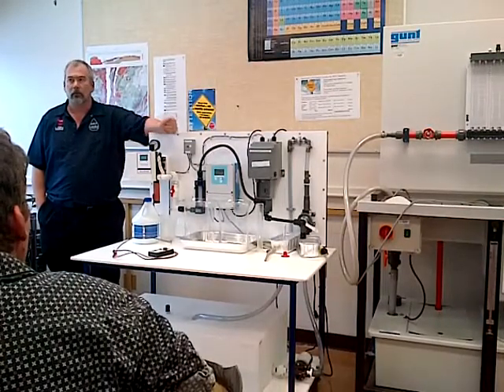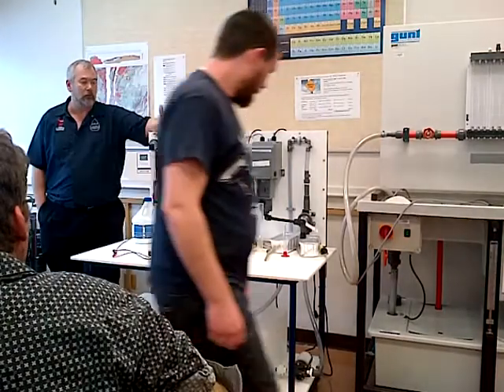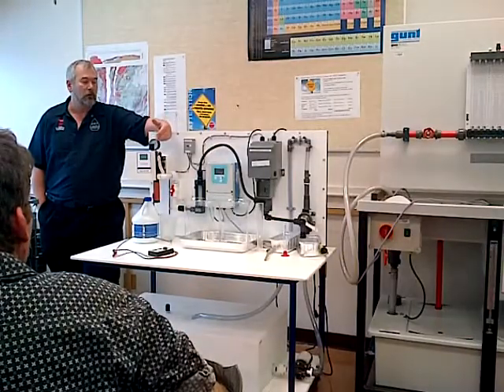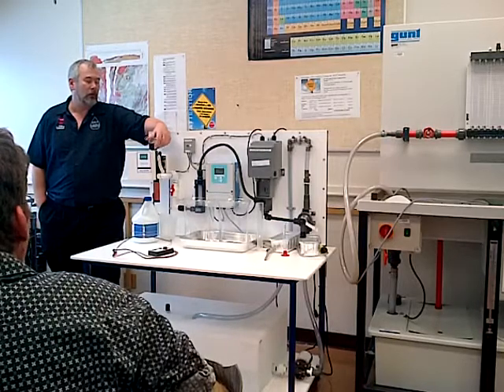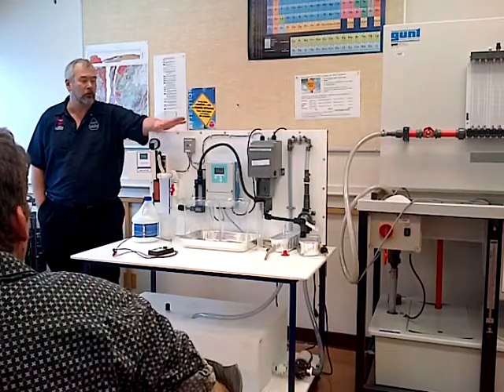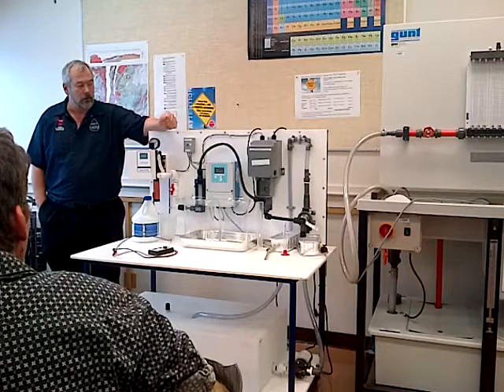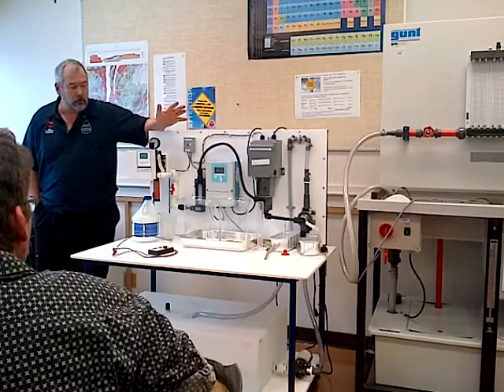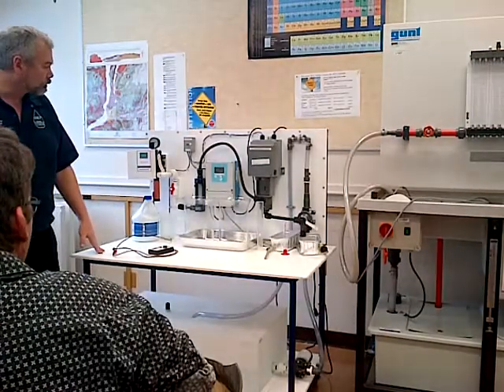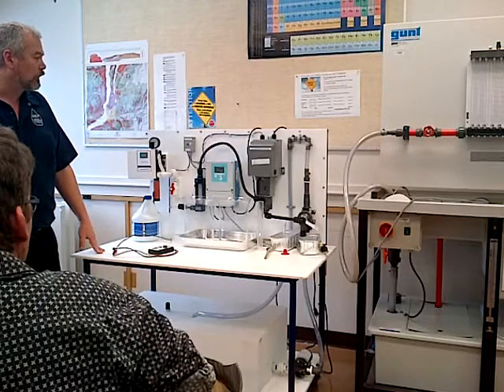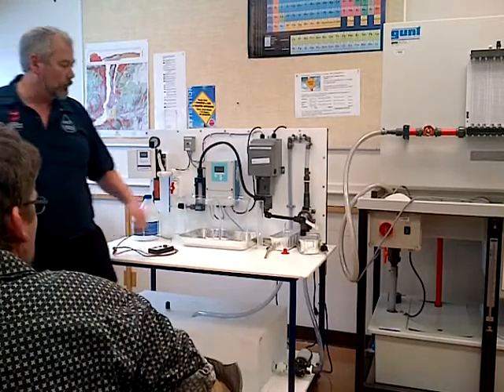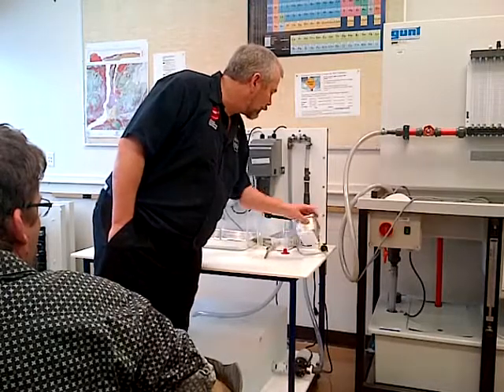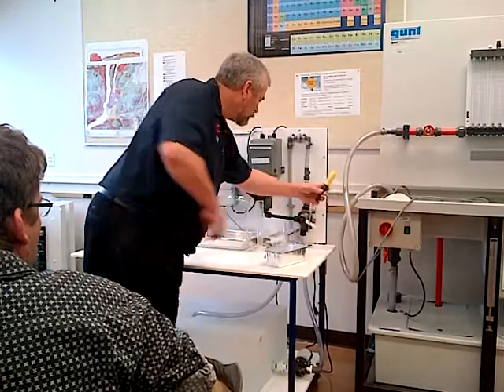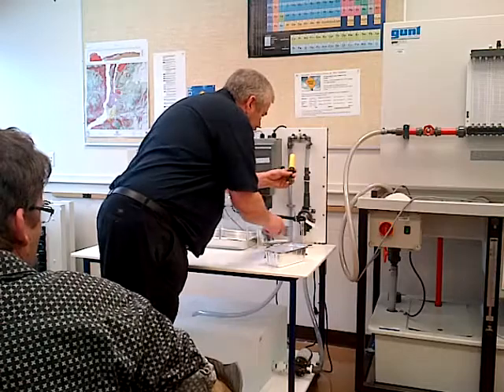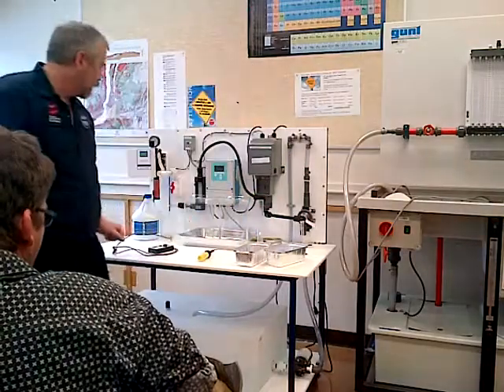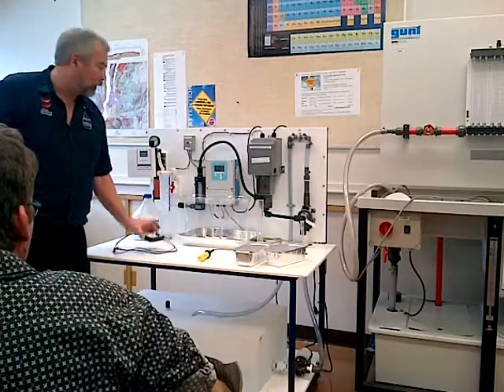Swapping out a chlorine, or it'll teach you how to switch tanks and the nuts and bolts of disinfecting water with chlorine. This one just basically gives you a short, sweet introduction to some of the instruments. So this is your chlorine probe. And this is just a 4 to 20 milliamp signal.